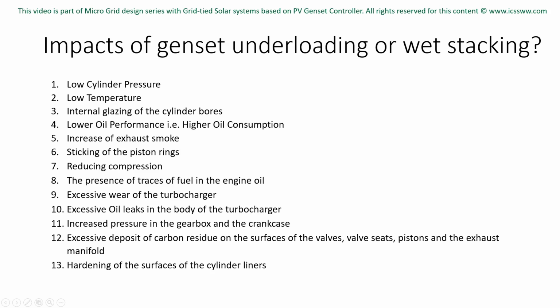Number 4. Lower oil performance. High oil consumption. Low load operation wreaks havoc on the engine's oil distribution system in a number of ways. Hard carbon deposits formed as a result of poor combustion cause bore polishing, destroying the honing marks for the oil. The oil burns and oil consumption increases. Due to the poorly sealing piston rings, unburnt fuel contaminates the lubricating oil, as do condensed water and residue, which cause a destructive acid buildup.